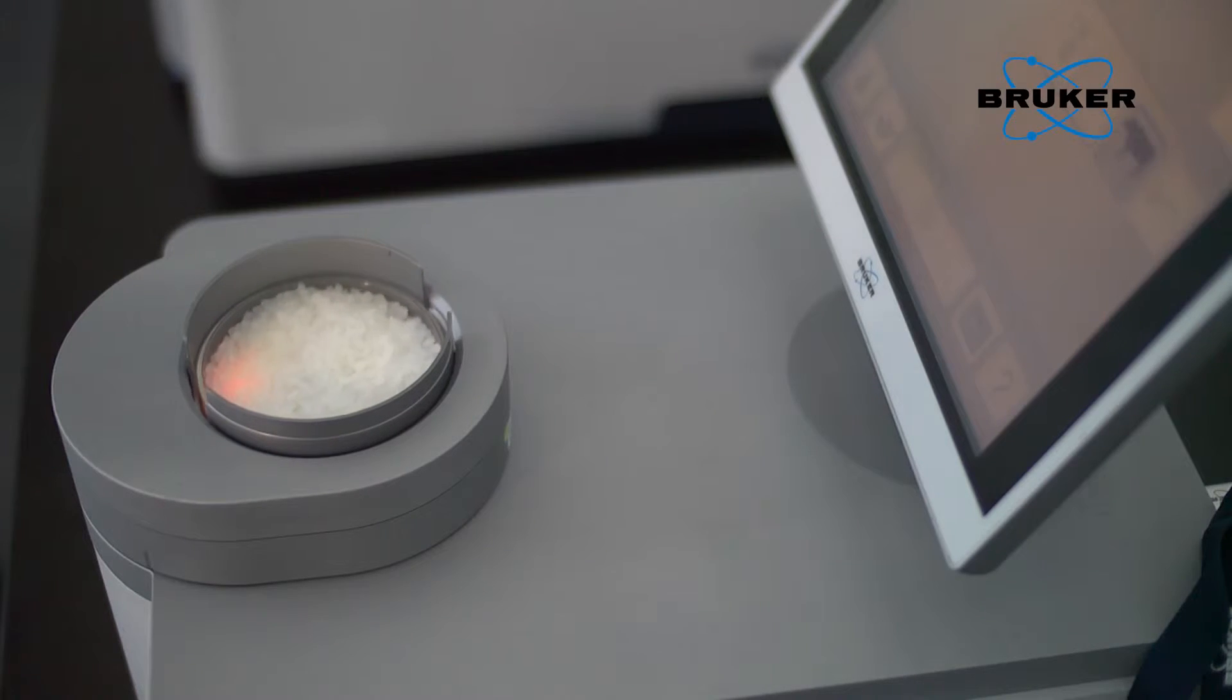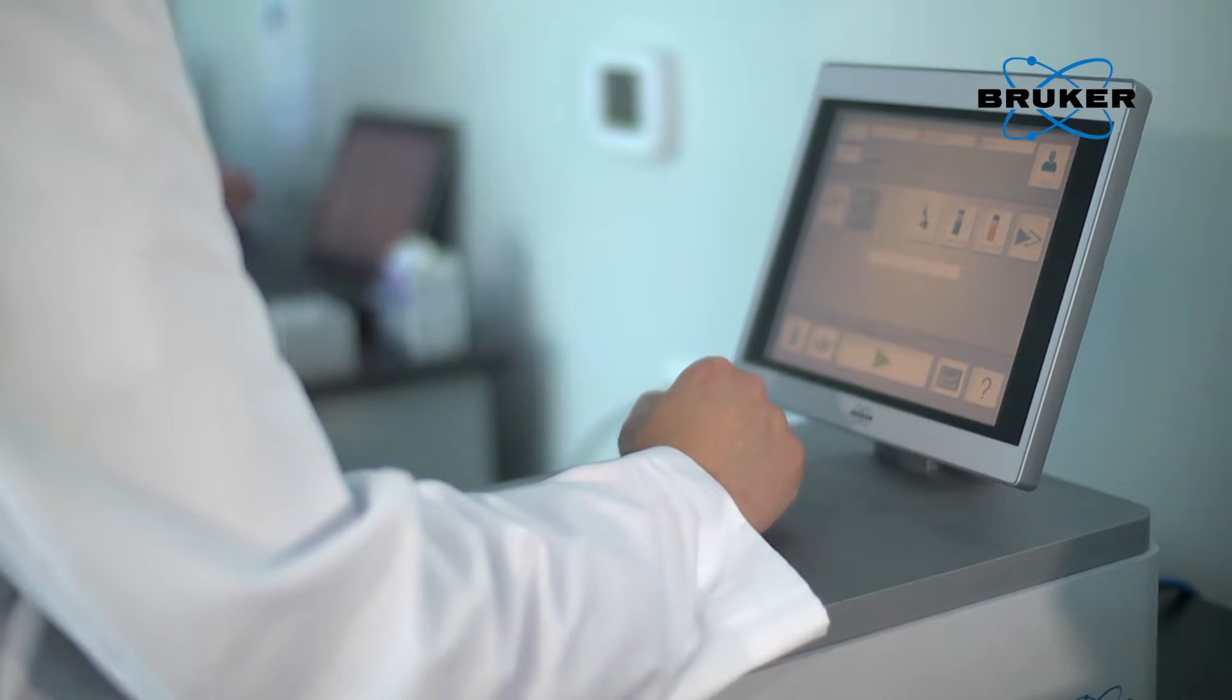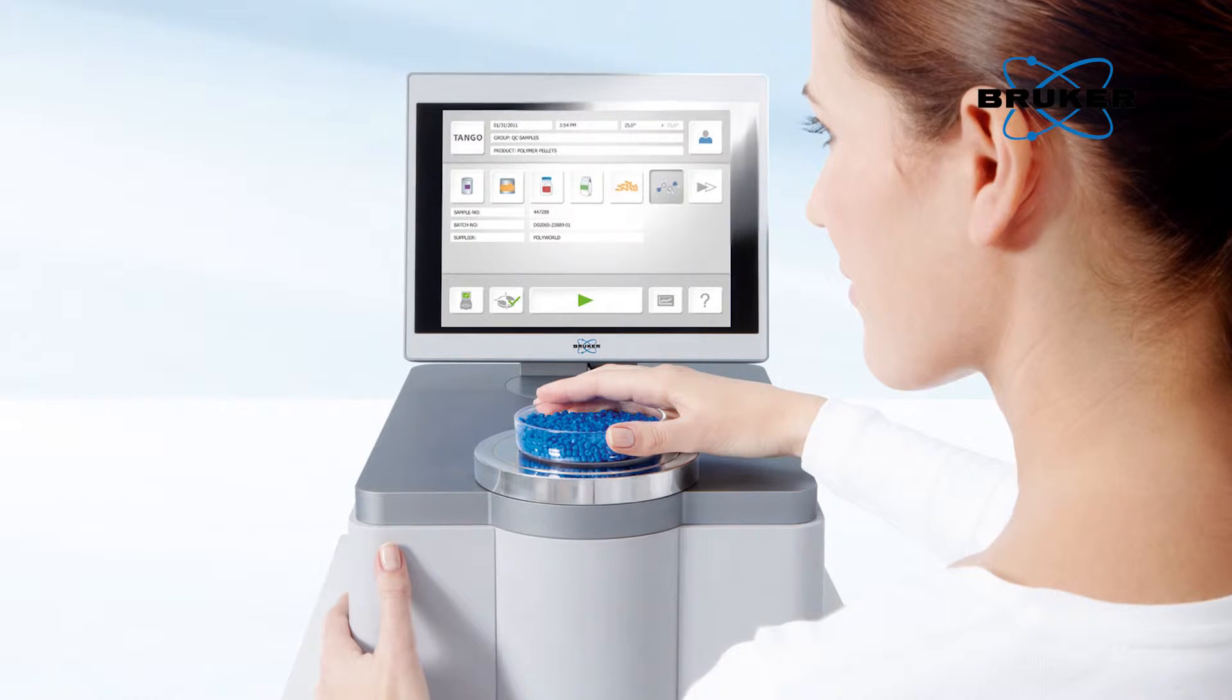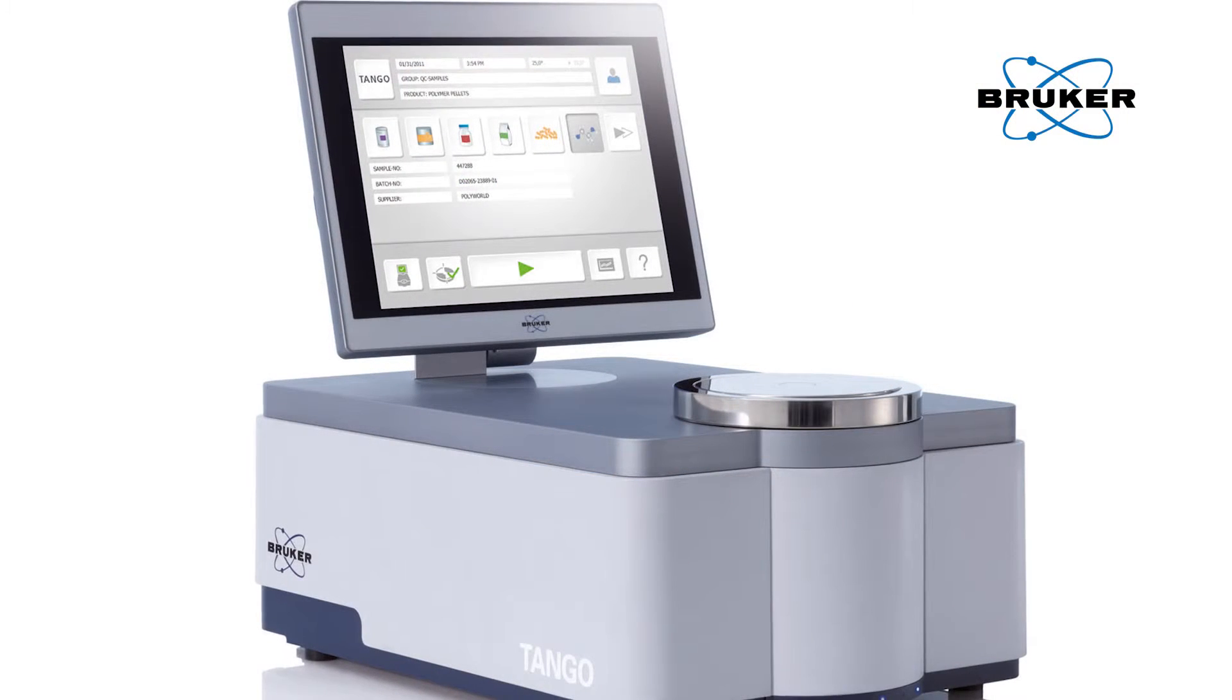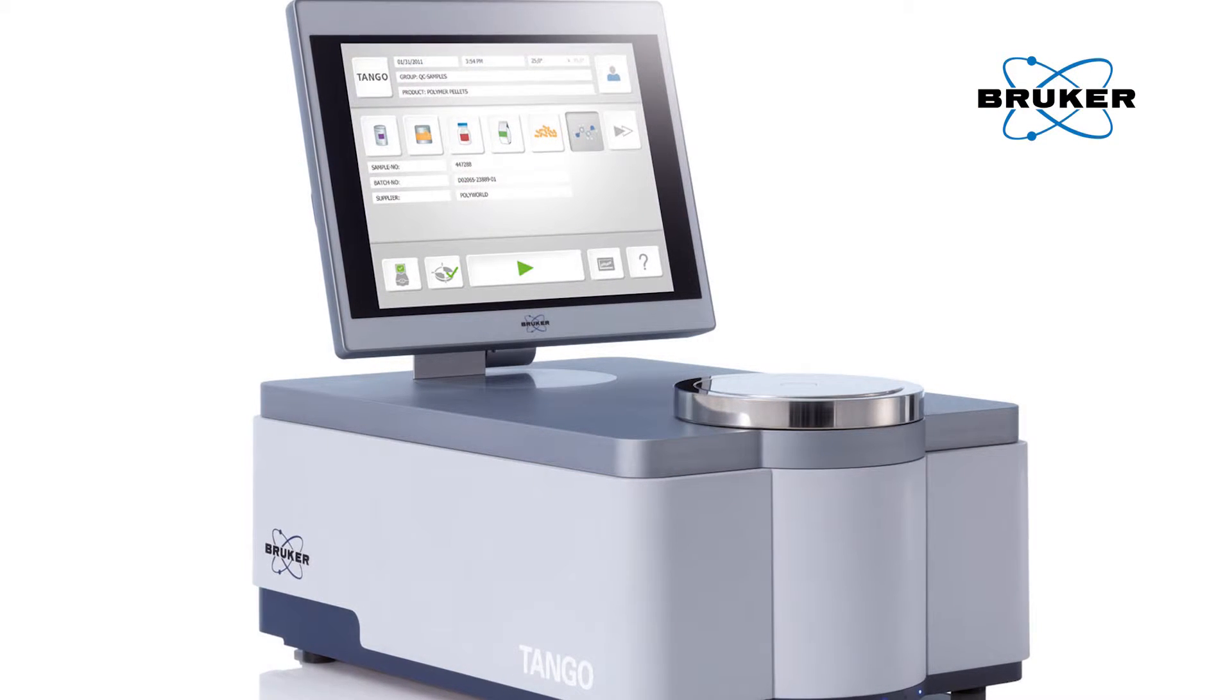The methods, or the calibrations that you have on the Tango, can be qualitative or quantitative, or both. This is a big advantage of the Tango software, allowing for multi-evaluation predictions. The calibrations can be set up to identify your materials, as well as give multiple component evaluation, all from the same scan.